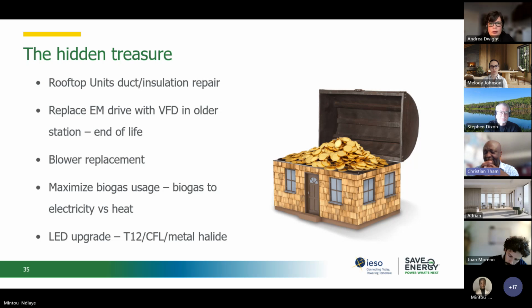In terms of air leaks, the rooftop units, duct and insulation repairs were also identified as savings opportunities. And Andrea said it, we did the math. For a small air leak, 15,000, or 15K per annum. That's a significant amount of money. And fixing that leak wouldn't cost you that much, but once you do it, you're going to see the savings.